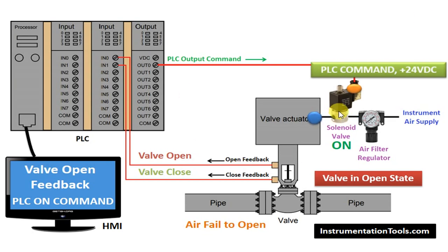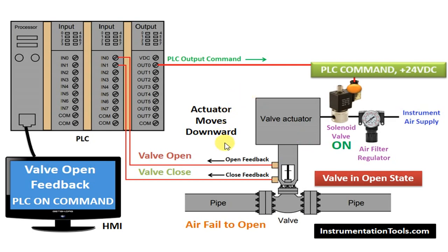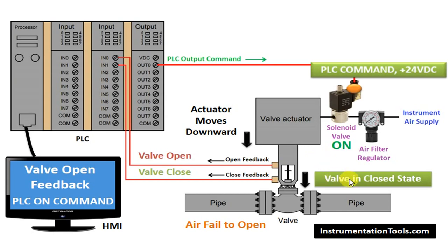As the SOV is energized, it will open the air circuit. So, it allows the input air from the SOV to the valve. Once the valve receives the air supply, the actuator in the valve — nothing but the diaphragm — will move, either downwards or upwards as per design. In our case, we consider air-fail-to-open, so it is already in open state. Whenever air is received on top of the diaphragm and activated, the air moves the diaphragm downwards so that the stem will move downwards to make the valve close. As the air comes to the valve, the actuator moves downwards. As the actuator moves downwards, the stem moves downwards, so the plug in the valve will close. So, the valve state will change from open state to closed state.